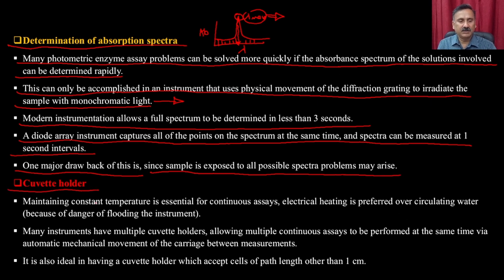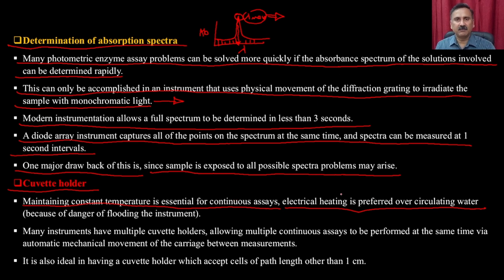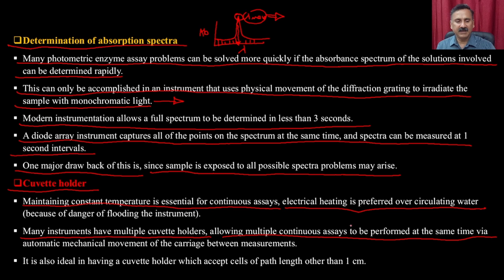Maintaining constant temperature is essential for continuous assays. Electrical heating is preferred over circulatory water bath because water circulation has more fluctuation. Many instruments have multiple cuvette holders allowing multiple continuous assays to be performed simultaneously with automatic mechanical movement of the carriage. It is also ideal to have a cuvette holder that accepts cells of path lengths other than one centimeter.